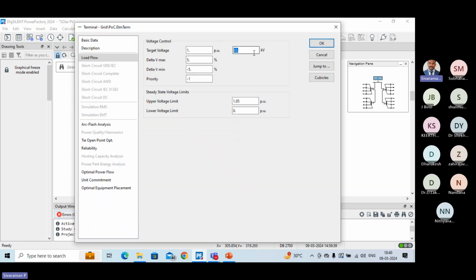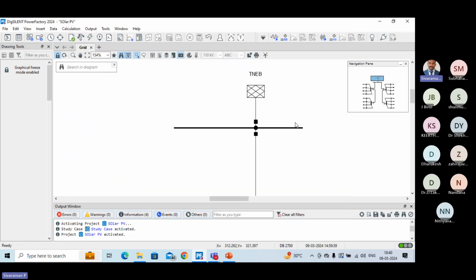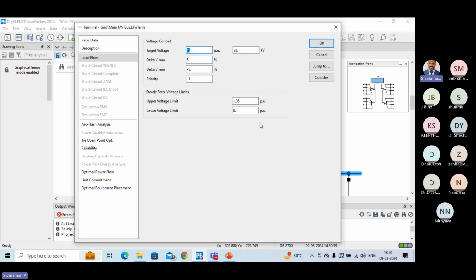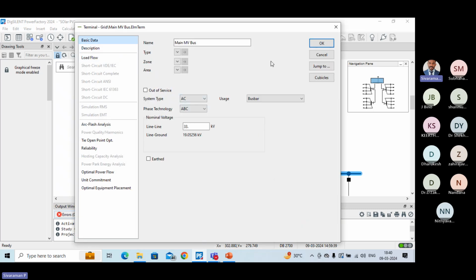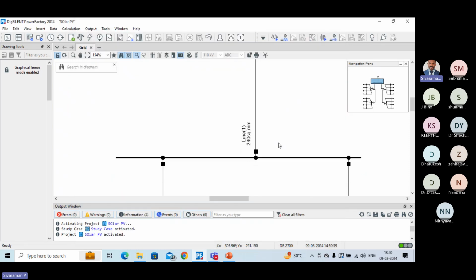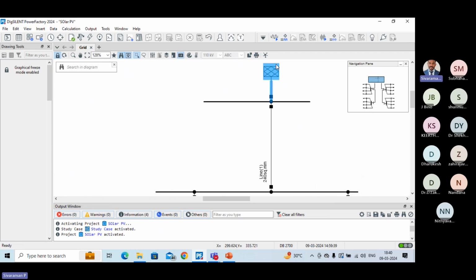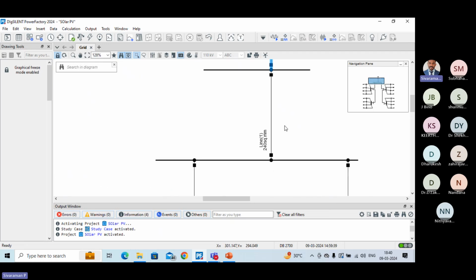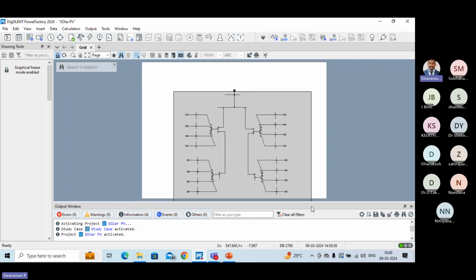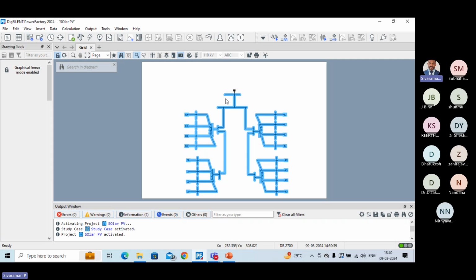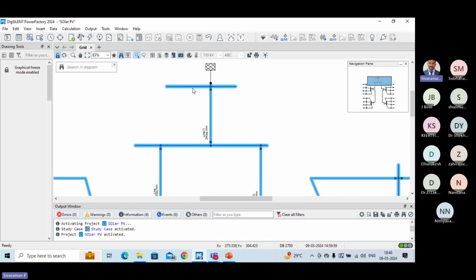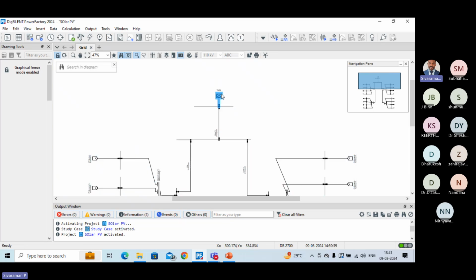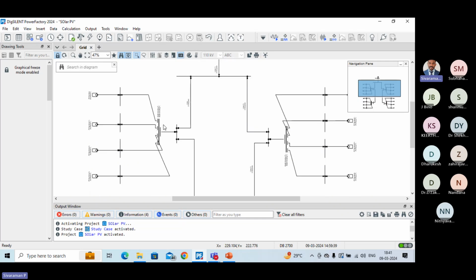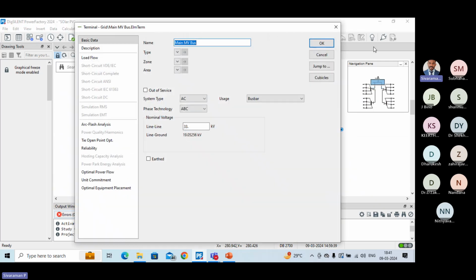This is at the 33 kV voltage level. Here there will actually be no substation. The power we are considering, we are exporting at the medium voltage of 33 kV itself. So our grid interconnection voltage is 33 kV. This will be the grid, and up to this portion will be our plant. Except for this grid, the remaining equipment will be our plant location. This grid will be at the substation of the TNEB.